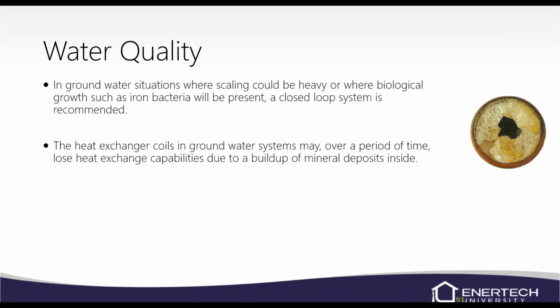Over time, on a closed loop it shouldn't, but on an open loop, your heat exchanger is going to scale up. You may have seen some scaling on water heaters sometimes in the old galvanized piping. It would look like a clogged artery. It shouldn't look that bad. If it does, you're going to have to replace the piping, because you'll never get that cleared up. But we do have the ability to clean them out and flush them out every once in a while, and that's why we put boiler drains on an open loop system.